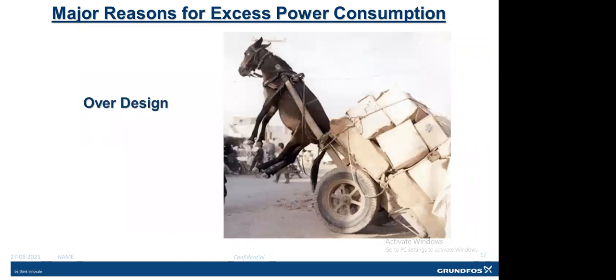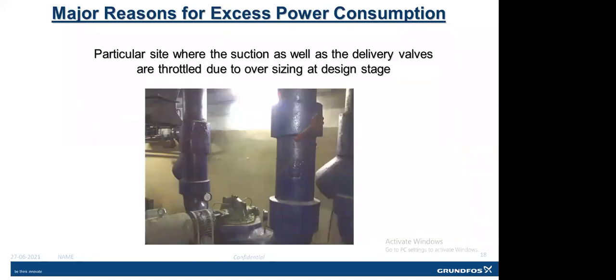Next common example is over design. Whenever we design a new pump, we take into account many safety margins. If our requirement is 80 cubic meters per hour, our consultant designs at 85, then our contractor designs at 90, and then the pump gets designed. These are common general practices. The pump gets designed at high flow and high head.